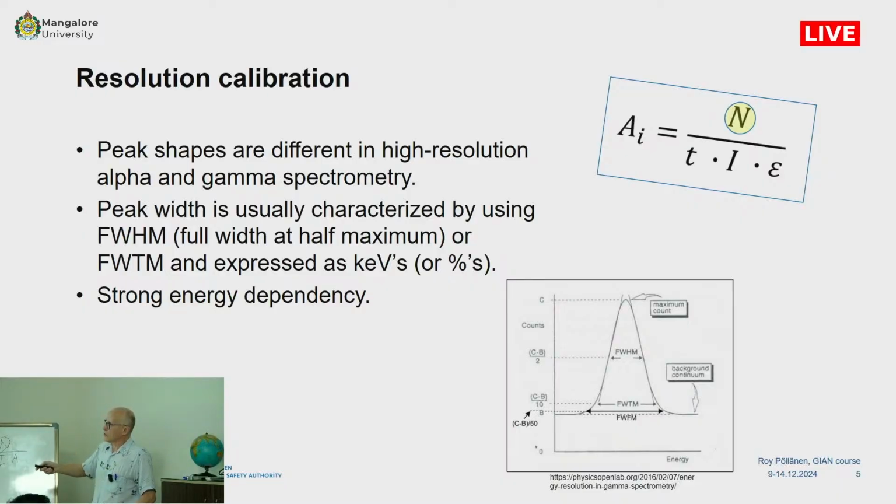But there is strong energy dependency, especially in case of scintillation detectors. At higher energies, the resolution is much wider than at lower energies. The effect is more or less same in high resolution gamma spectrometry, but not so stressed effect.